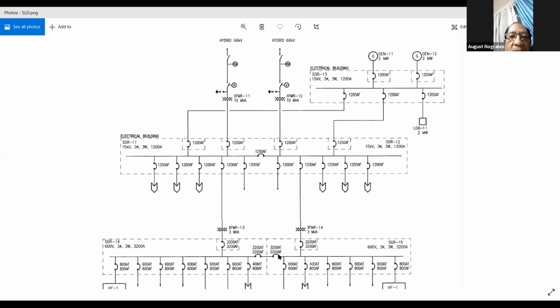Okay. So there is, depending on the requirement of the owner or the design. That's correct. Yeah, maybe it was specified as a hard spec requirement for a specific piece of gear, which would therefore mean that you end up with two ties there. If it's more of a performance specification where it could be more generic to any vendor or manufacturer's piece of equipment, you may not necessarily end up with two of them. It would depend on maybe how it was specified during the procurement phase.